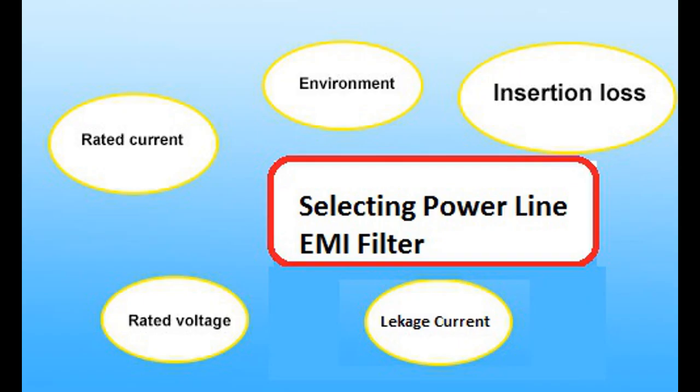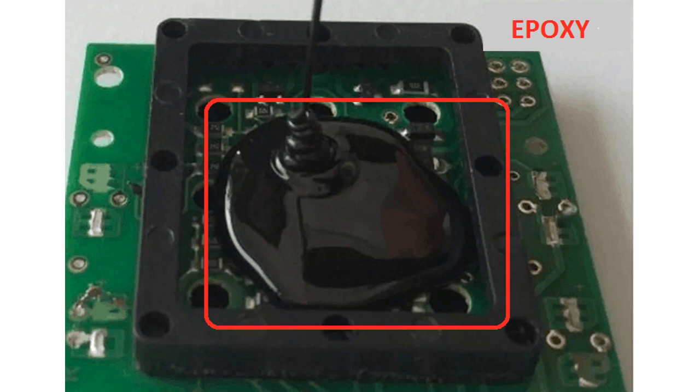When selecting the power line filter, three main indicators should be considered. First is voltage and current rating, the following is insertion loss, and finally it is size and structure. Since the filter inside is typically epoxy-potted, environment is not a main concern.